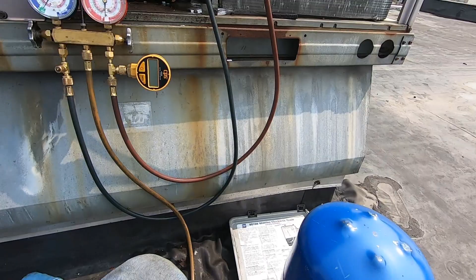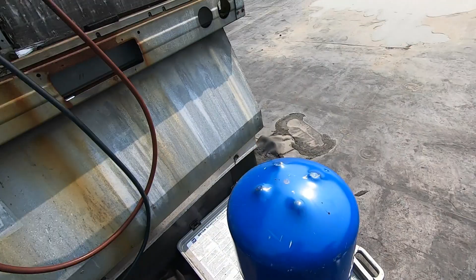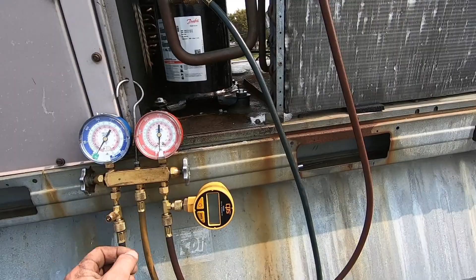This unit holds 9 pounds of R22. We're using 422B, and my experience with this, I've had to overcharge it almost every time. So I've got my refrigerant bled out to my manifold. We're gonna go ahead and put the 9 pounds in, start there. More than likely I'm gonna have to add, but we'll get to that when I get the unit running. So let's go ahead and let it loose.